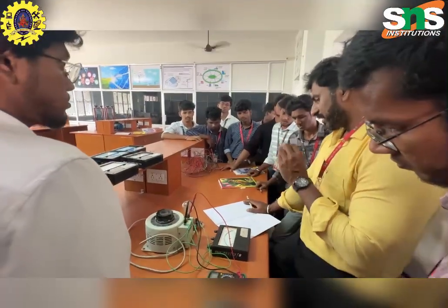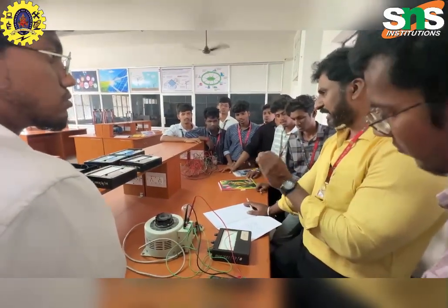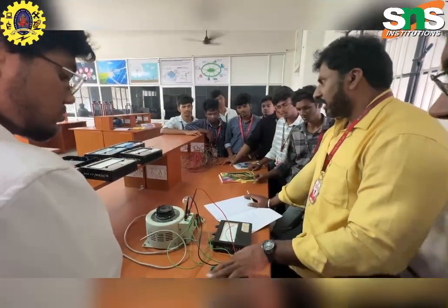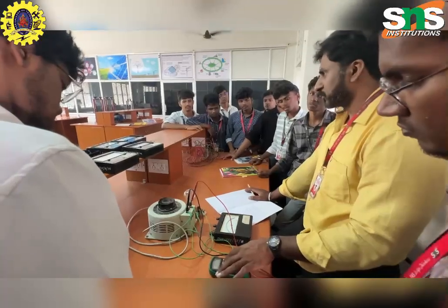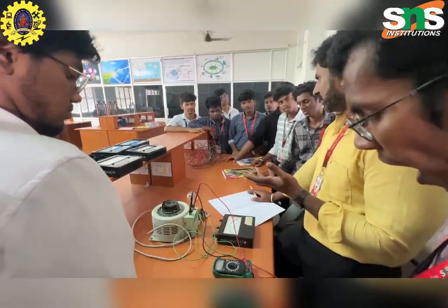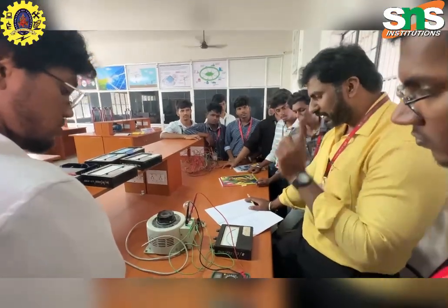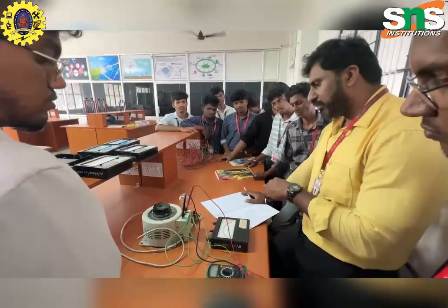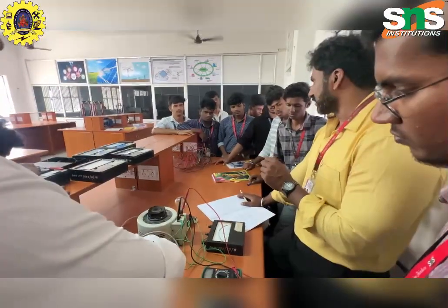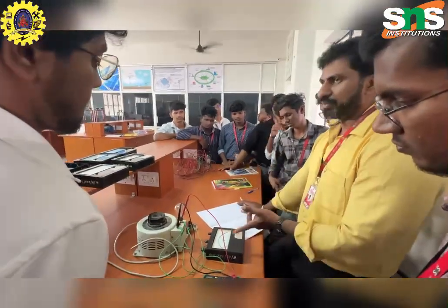When we are calibrating the meter, we need some kind of standard meter, because based on the standard meter only can we tell whether the meter is reading right or wrong. Now we are taking the standard meter as this multimeter. But in real time, the standard meter is available in national laboratories. We give the meters to those laboratories and the meter is calibrated with the help of a standard meter. After calibrating, they give a certification. That certification is valid up to 1 year. In that 1 year, the meter value will be correct. After 1 year, again we need to calibrate the meter, right?